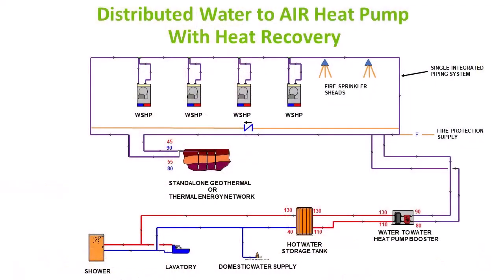Anybody ever done it? No? I've done a bunch of these. It's been in the NFPA, Chapter 13 — I don't remember the paragraph number — since the late 1970s. He worked for the company that patented this system. It was called Tri-Water, American Air Filter. So that system's been around a long time, and here we've gone from 2 to just 1 pipe, but that pipe isn't even the HVAC pipe — it's courtesy of the fire sprinkler system.